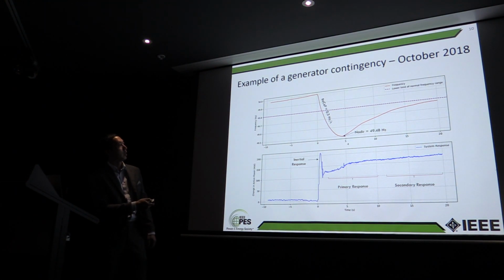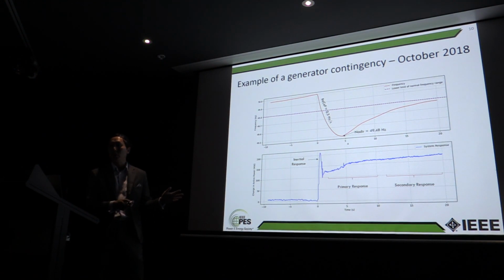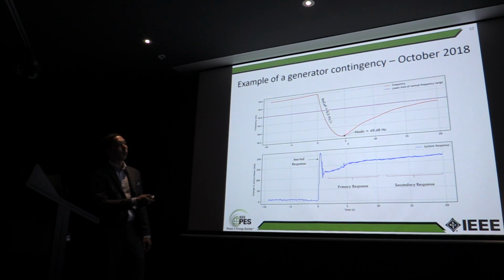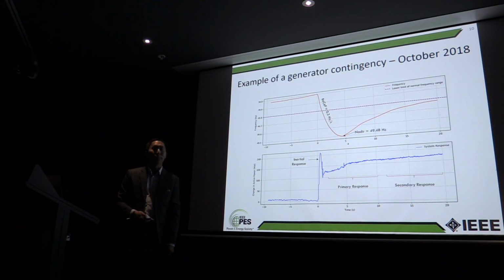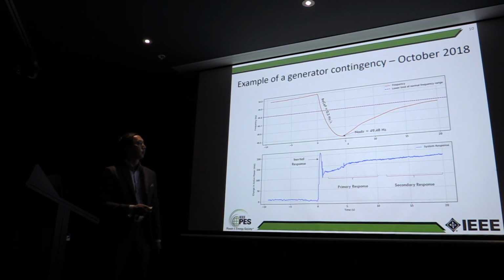So you can see this is a 200 megawatt generator dropping off in this case. We had a RoCoF here of 0.3 hertz per second, a frequency nadir of 49.48 hertz, but then it recovered very quickly and we were all done in 20 odd seconds.